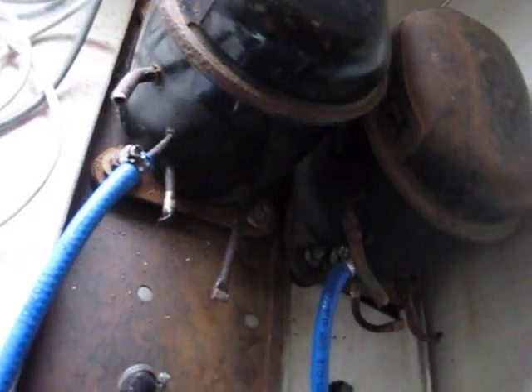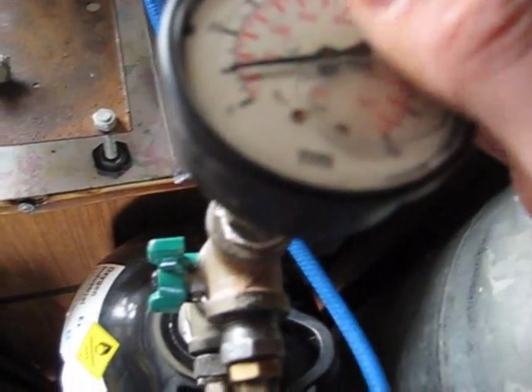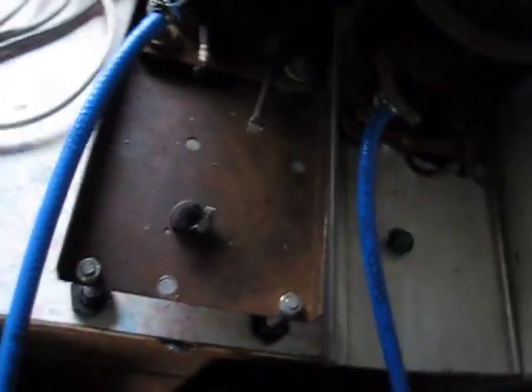You've got pressure on it so it's alright. The nameplate reads E107-1, and this one is an E106, so this must be an older model. It's got about 150 PSI in there so far. About 150 PSI on the drop - no fluctuations, it's accurate. Let it go to push for a bit - okay, about 15 minutes later, it's about 280 PSI. That's pretty good.